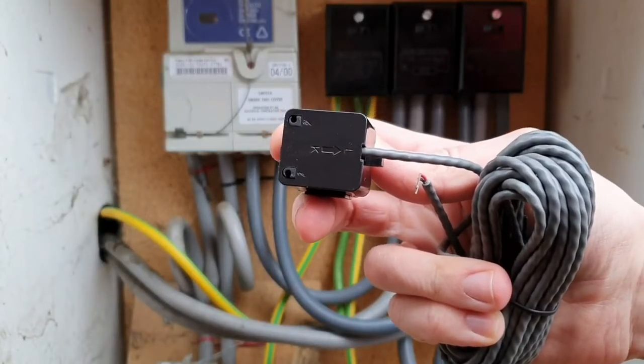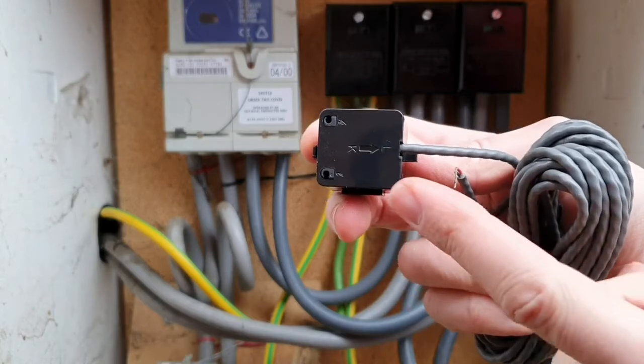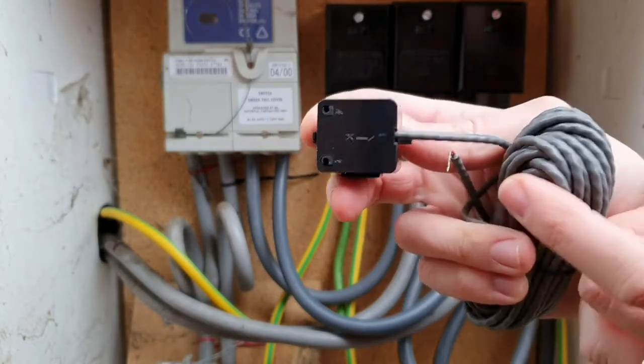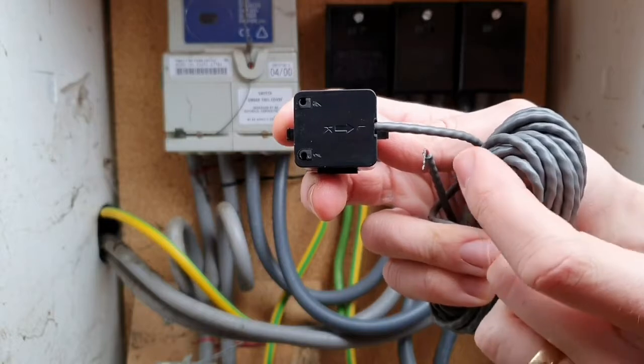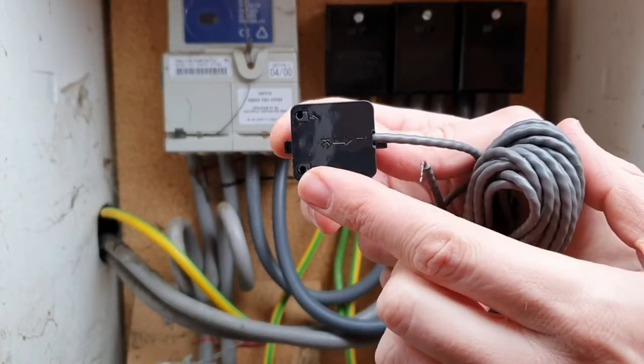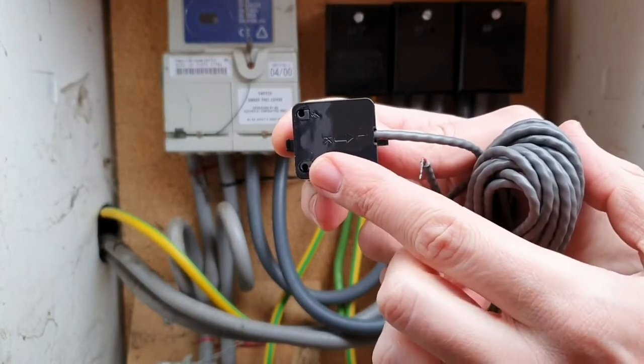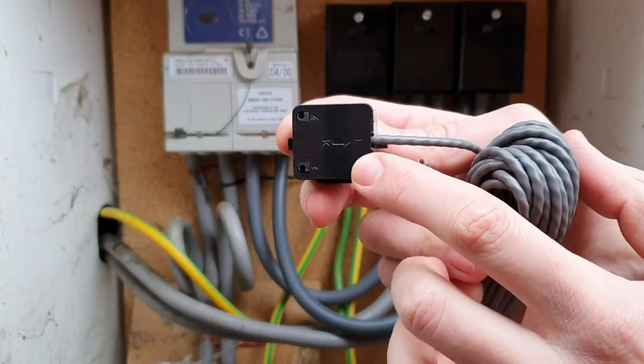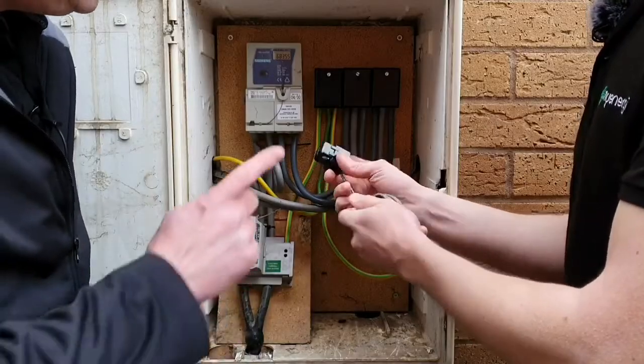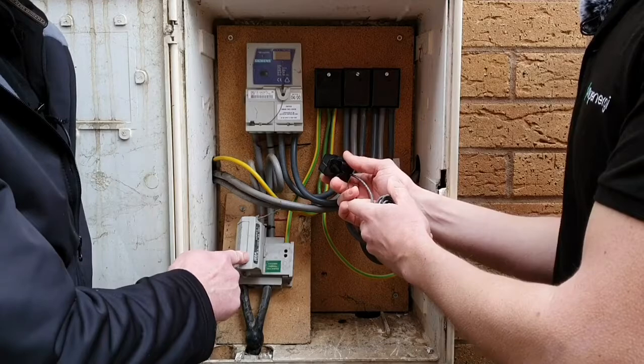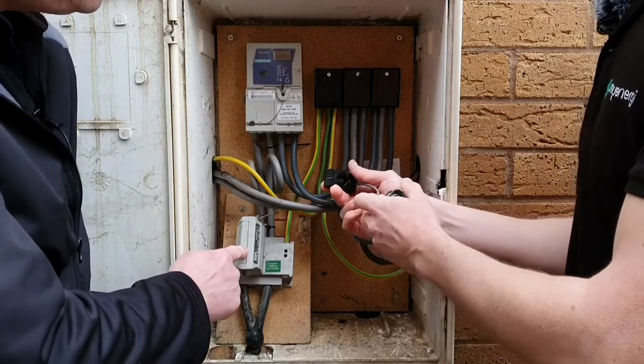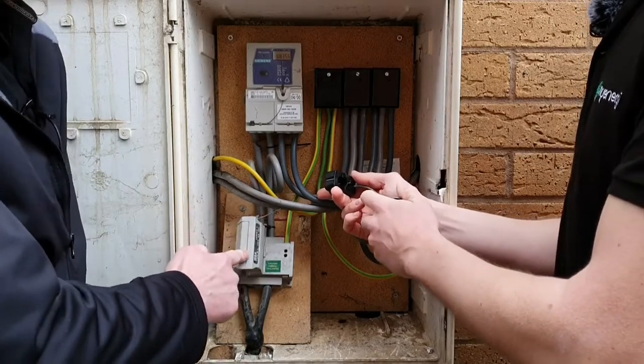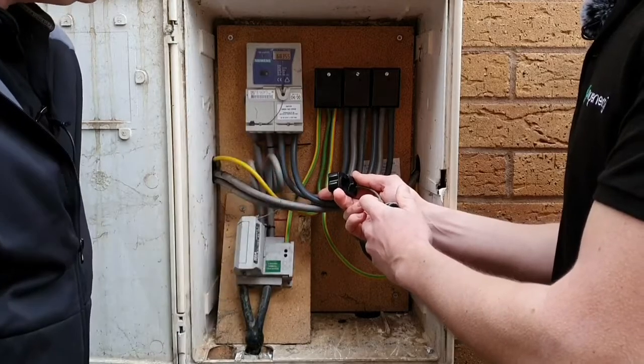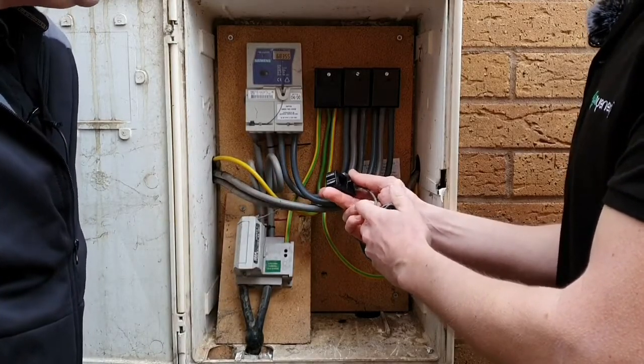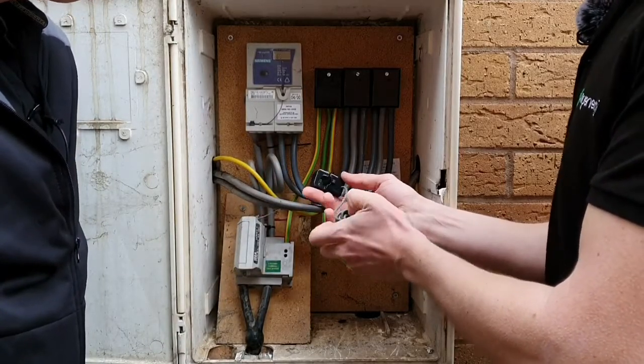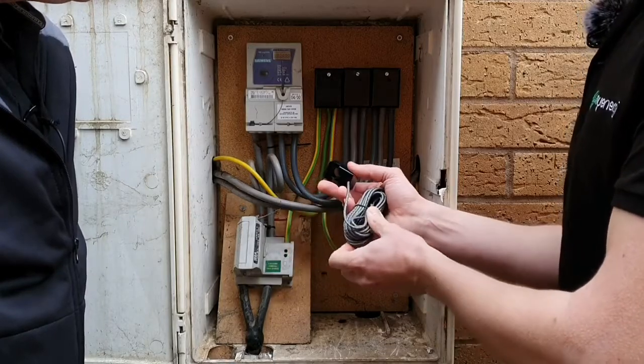Now this is an absolutely critical piece of kit because it speaks to the Zappi and it tells the Zappi how much current is flowing into the installation, and the Zappi then very cleverly controls how much current is flowing into the car charging system. And that's really important because we don't want to overload the fuse here. The incoming cutout fuse doesn't want to be taken more than its rated value, and this CT will help us do that, Joe. Absolutely. So it'll monitor the current and make sure that it stays at acceptable levels from the car charging point of view.